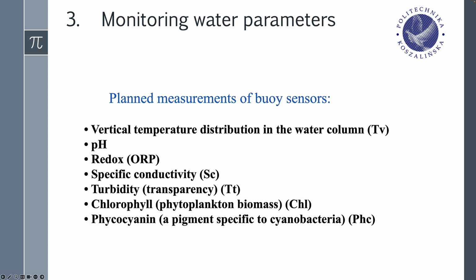Turbidity, transparency, TT. The transparency measurement is carried out using the emission of an infrared light pulse, with a wavelength of approximately 850 nm, in the direction of a detector sensitive to infrared radiation. The suspension in the emission field absorbs the radiation, reducing the amount of light reaching the detector. The more suspension, the proportionally less light received, indicating a higher level of turbidity.